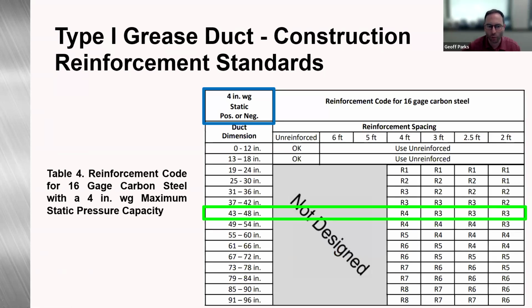So if we jump back to table 4, we look at our 48-inch duct dimension. As you can see, the first thing we come to is the 4-foot reinforcement spacing, and that's telling us we need an R4 reinforcement. If we looked at 3-foot spacing down to 2-foot, we could get away with an R3 reinforcement. And anybody familiar with the industrial duct construction knows the stiffeners are R1, R2, R3, R4 versus an A, B, C, D in the HVAC duct construction standards. So 48-inch, we need an R4 at 4-foot spacing.